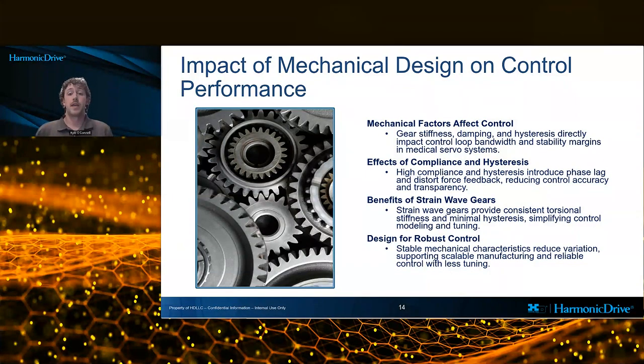So, the impact of mechanical design on control performance. Mechanical design choices have a direct, and sometimes underappreciated, impact on servo control performance in medical systems. Gear stiffness, damping, and the hysteresis of gear systems influence achievable control loop bandwidth and stability margins.